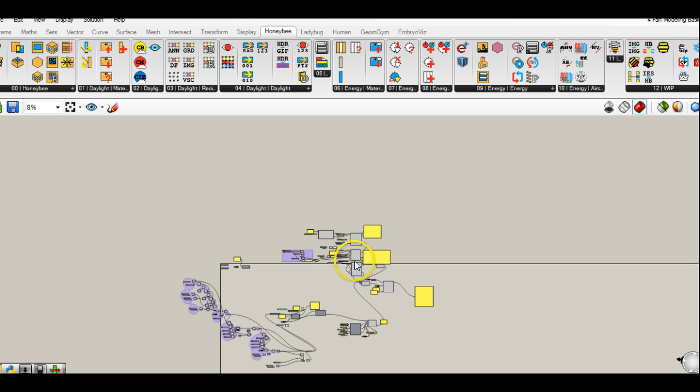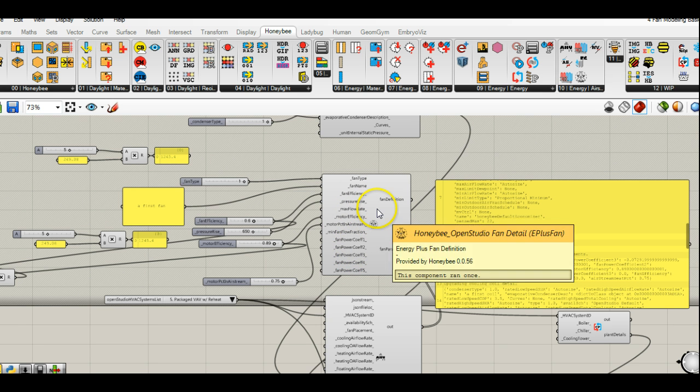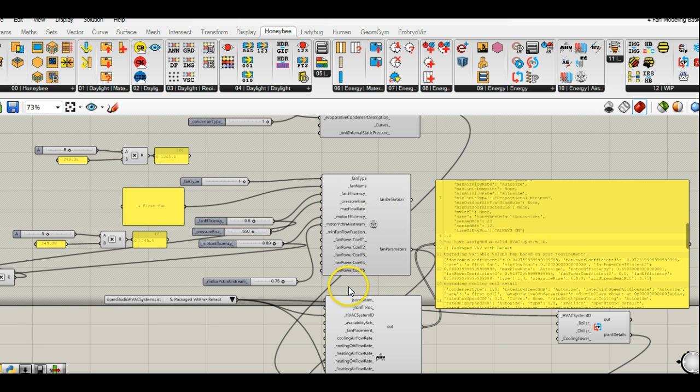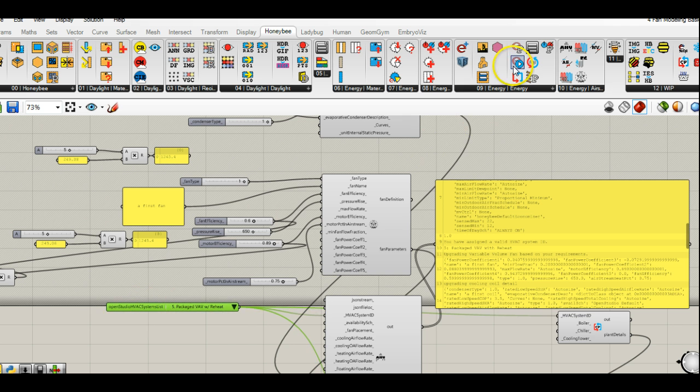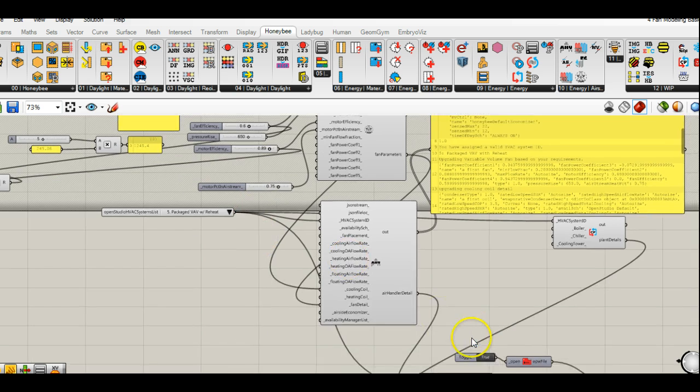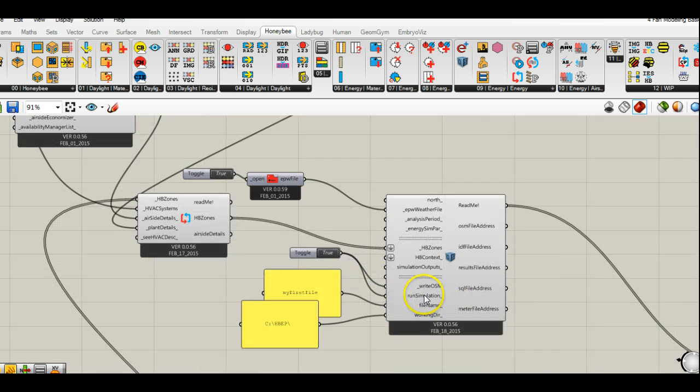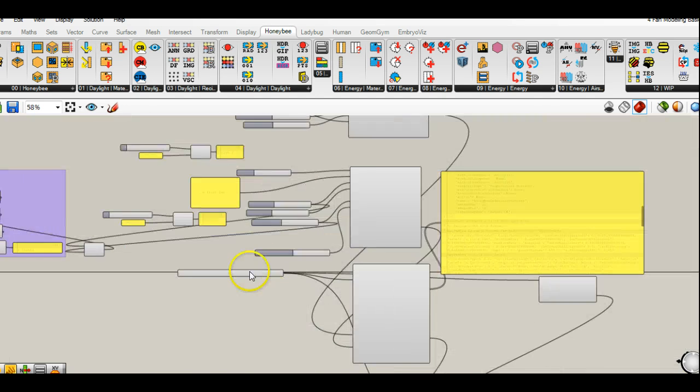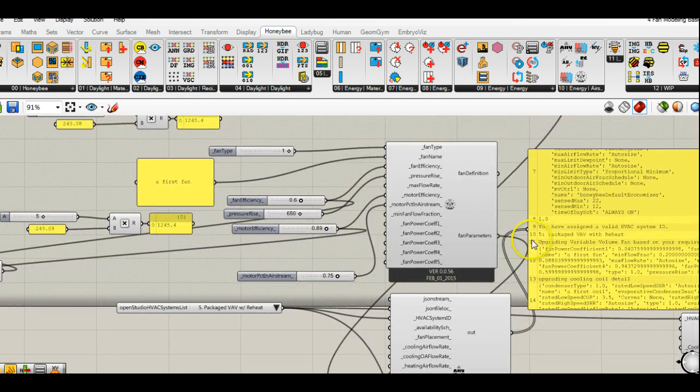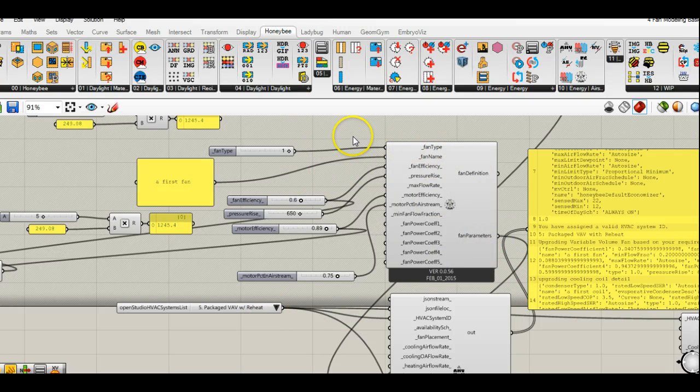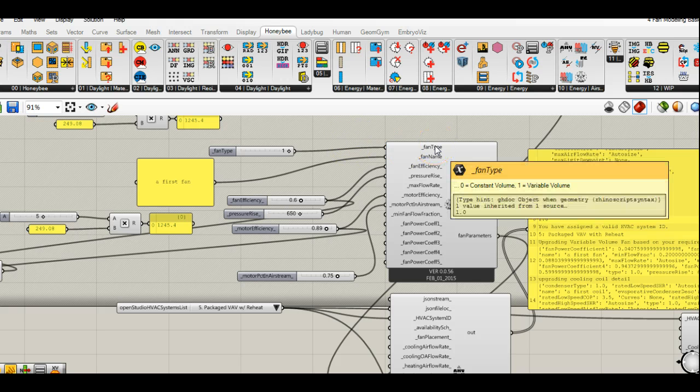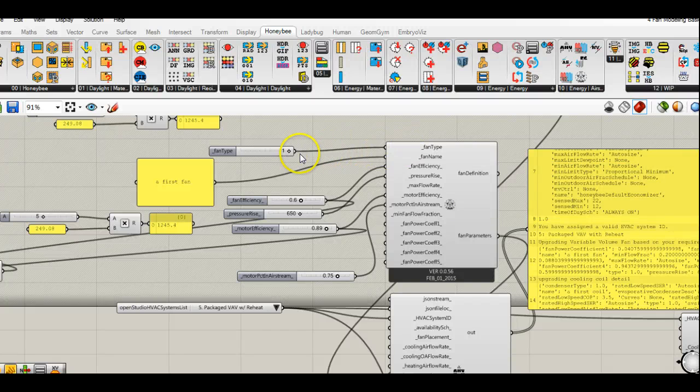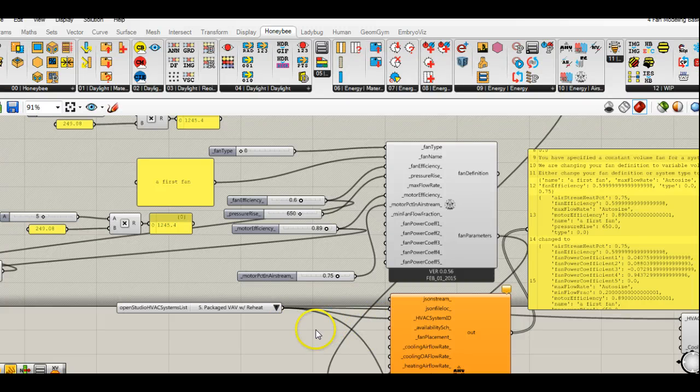Same group of components that I had gone through in earlier lectures. The fan component is right here. The HVAC system list that comes from this dropdown is connected to a number of different components, and you'll get a warning if you mix and match the wrong thing. You can either choose zero for constant volume or one for variable volume. If I were to change this to zero, you'll see that the downstream component will say that's the wrong type of component, this is expecting a variable volume fan.